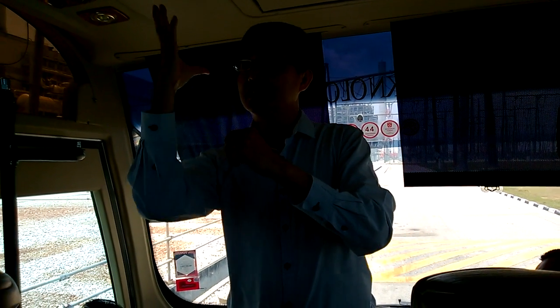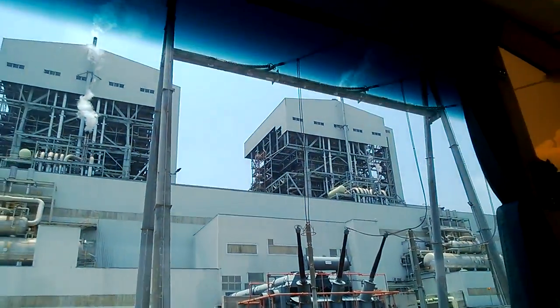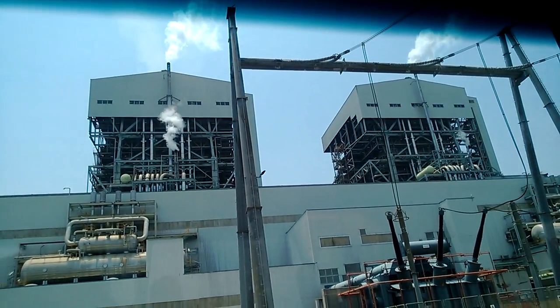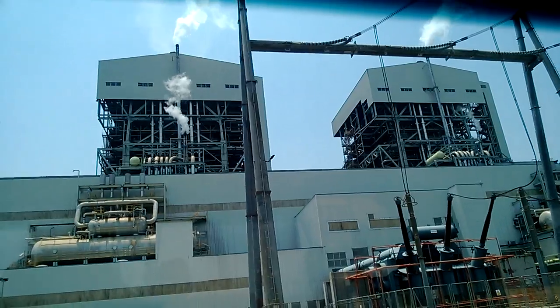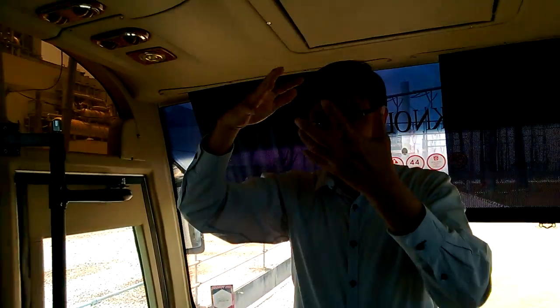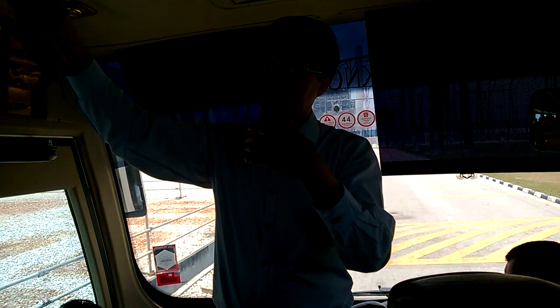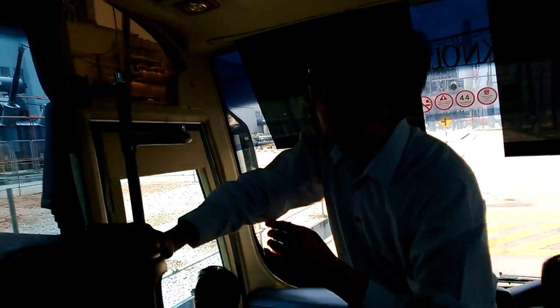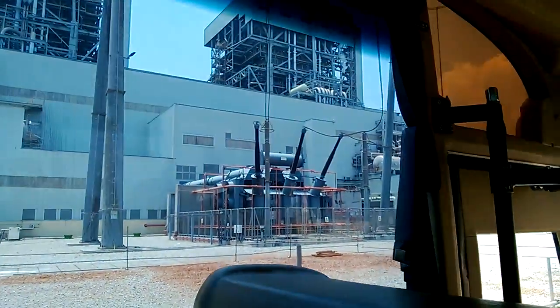That blown out water, high pressure water and temperature, is discharged. Part of it, because it's high temperature water and pressure, some of it, half of it, flashes into steam and it comes out there, the top one. So the other half, which hasn't flashed into steam, is hot water, which we have to cool down before we can discharge it. The temperature of water we discharge from here cannot be more than 40 degrees C.